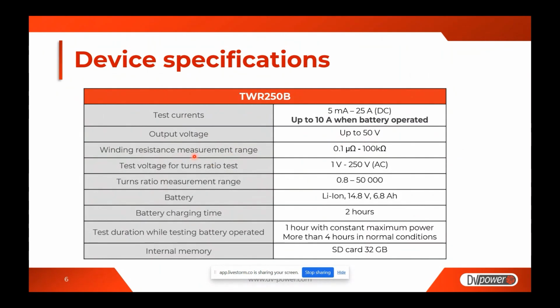Winding resistance measurement range, you can see in this table, it will be able to cover the majority of transformers up to 100 kilo ohms. For turn ratio test, voltage will be up to 250 volts AC. The same turn ratio measurement range we could see with our turn ratio testers, so up to 50,000 turn ratio maximum.